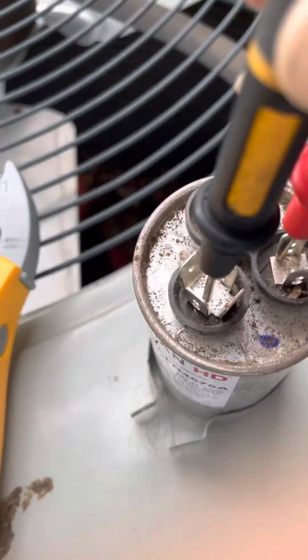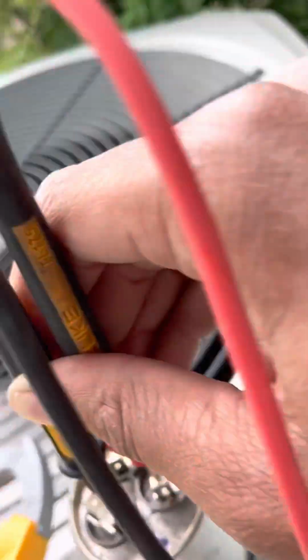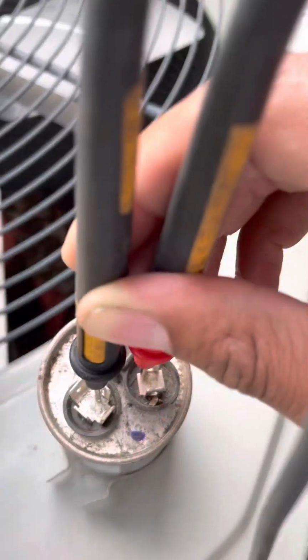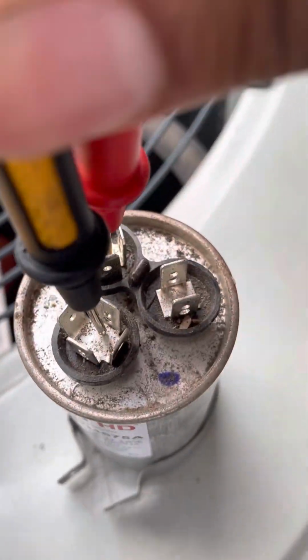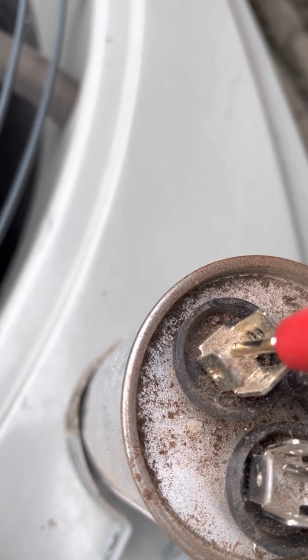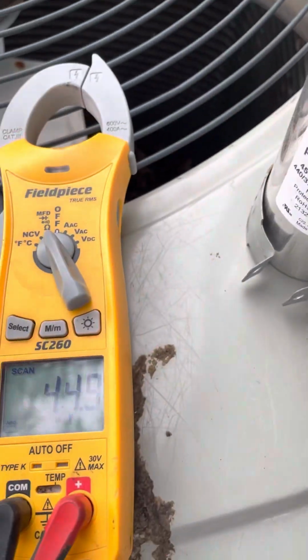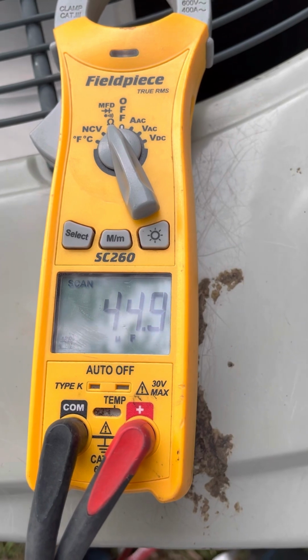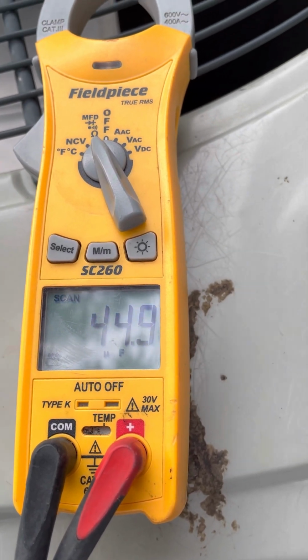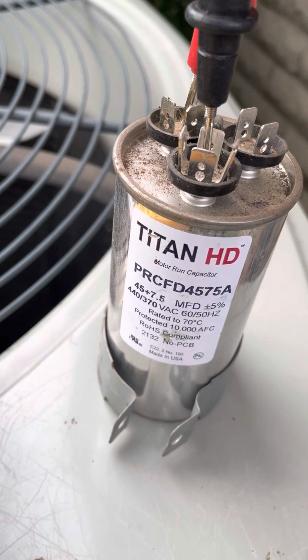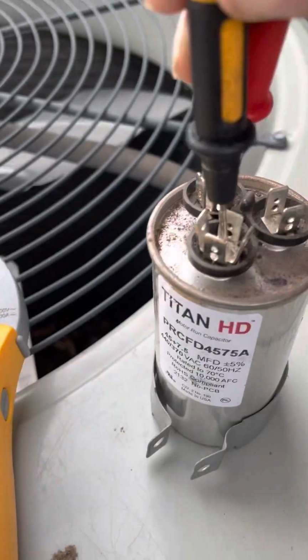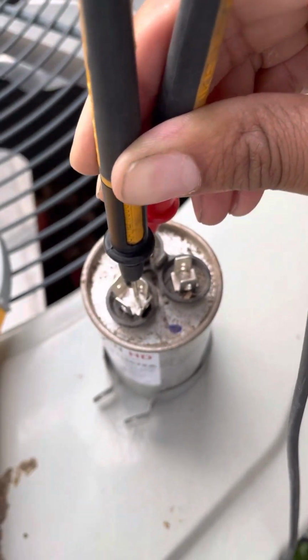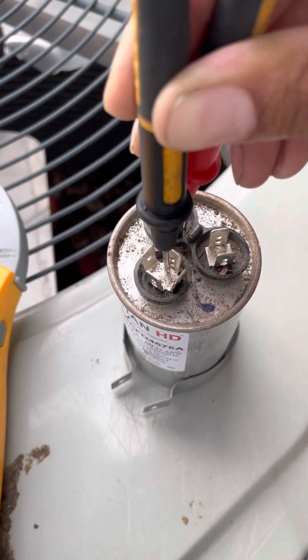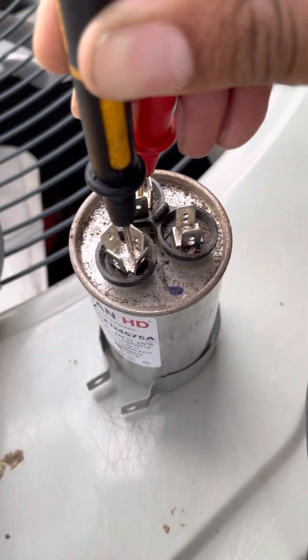We're going to keep one lead on common, and then we're going to move our other lead to the compressor, or the Herm terminal, as you can see there. And you can see we have 44.9. And again, we're rated for 45, so we are within range there. Pretty simple. That's pretty much it. That's how you properly check a capacitor.